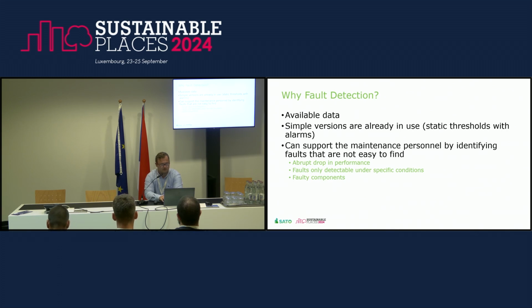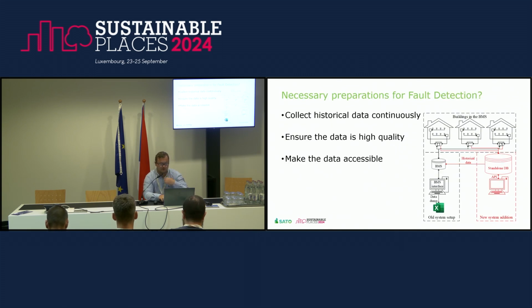In order to do fault detection, you need available data. What we found out in this project is, even though our building is one of our case buildings from 2016, so quite a modern building, we still had no way of collecting or storing historical data older than generally one month, and only for a few data points. The reason is that in the building management system, everything was stored locally, with realistically no way to expand the storage.